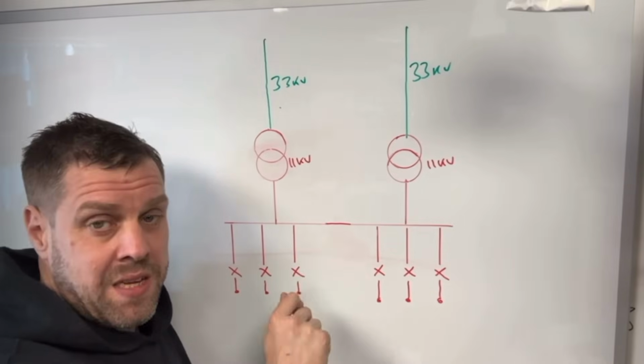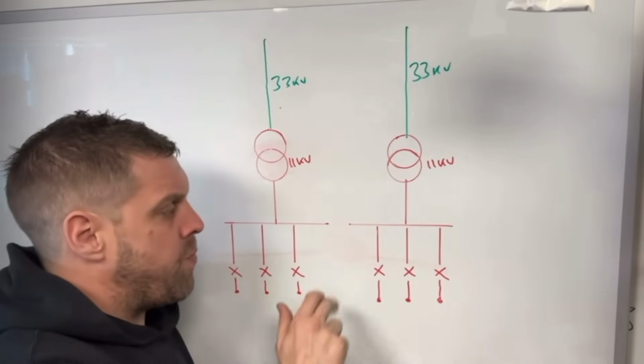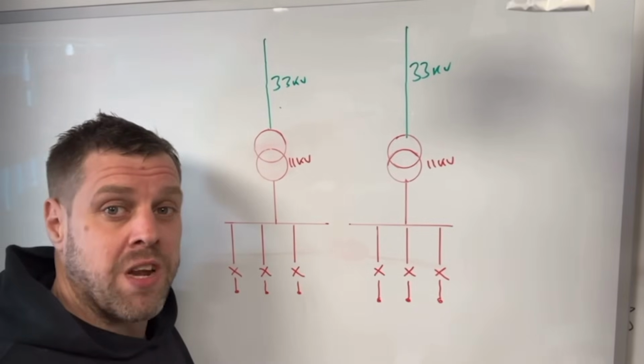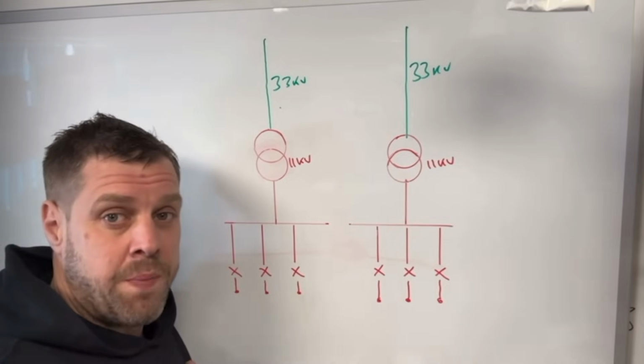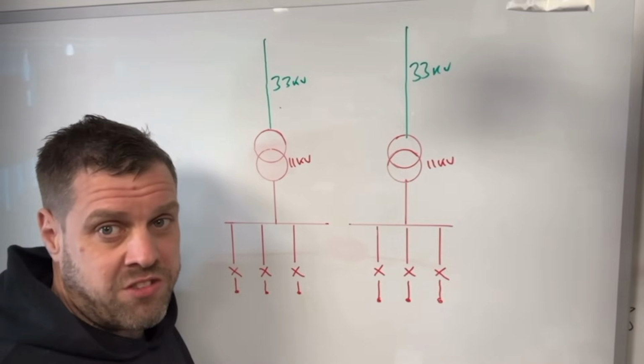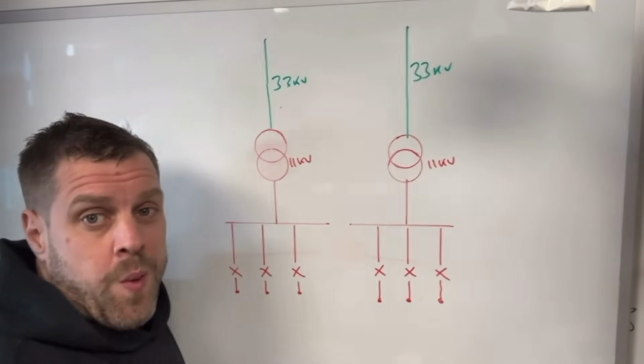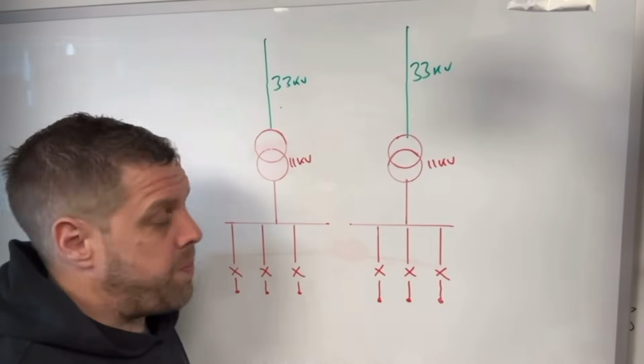Now generally we keep the bus section open because it keeps the fault current level down. There are ways of keeping it shut, but you have to come up with clever protection to do that. So we've already stumbled upon a point there. Remember, don't kick the tripod.